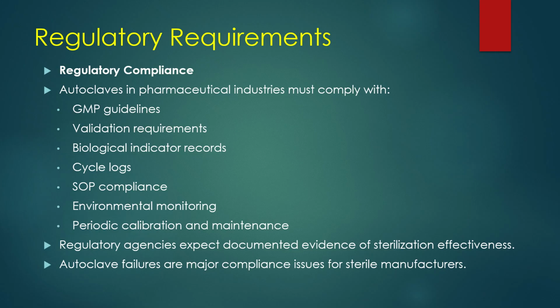Let's see regulatory requirements. Autoclaves used in pharma manufacturing must comply with GMP requirements, validated sterilization procedures, and approved SOPs. Compliance also includes maintaining cycle logs, biological indicator records, environmental monitoring data, and documented periodic calibration and preventive maintenance to ensure consistent sterilization performance and regulatory readiness. Regulatory agencies expect documented evidence of sterilization effectiveness. Autoclave failures are major compliance issues for sterile manufacturers.